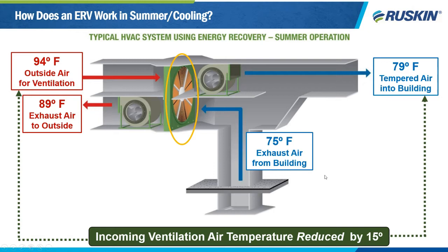In a traditional system without a heat exchanger, in this example we are using a wheel as a heat exchanger, I'll show you a core in a second. Without using a heat exchanger, you would traditionally be exhausting that 75 degree air straight out of your building. Additionally, you would be taking that 94 degree air straight into your rooftop unit, into your fan coil, and then have to cool that 94 degree air down. You already spent a lot of time and a lot of money cooling down that 75 degree air in your space. Why not recover some of that energy? And that's exactly what the wheel in this example is doing. Your incoming ventilation air temperature is reduced by 15 degrees. Next slide.